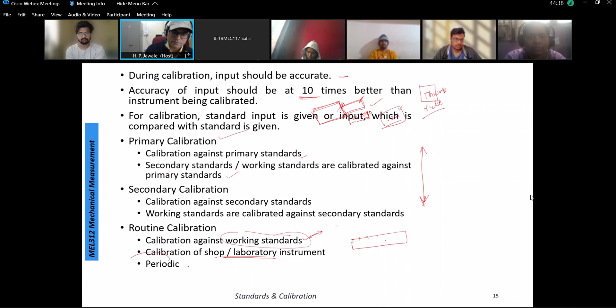It is a flow meter to be calibrated. Then in the flow meter, what is there? The process is fundamentally governed by volume of the fluid or volume of the element flowing per given time. So volume and time are the entities which are under measurement independently but simultaneously measured and then calibrated with the primary standard. So if it is a flow meter to be calibrated, we are going to measure volume and time independently with 2 different equipments or 2 different measuring systems. Simultaneously we are going to measure, and we are going to measure that with the primary standards available with us for measurement of time and measurement of elements in the volume measurement.